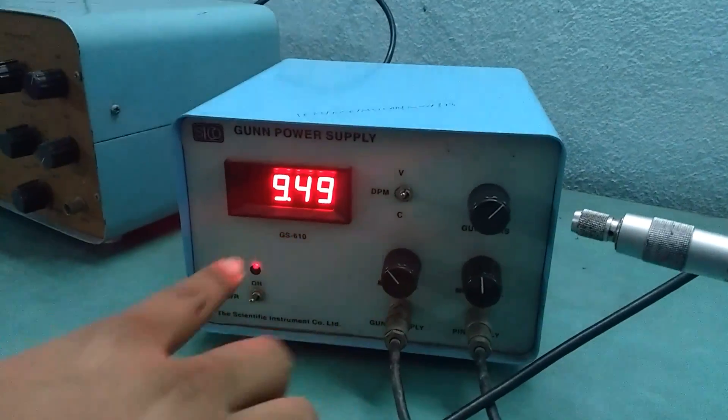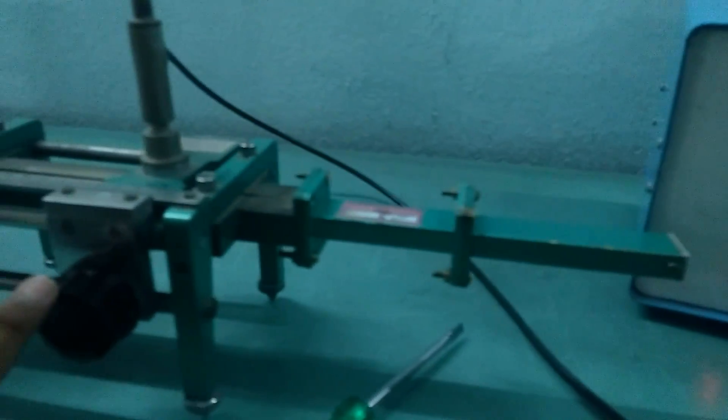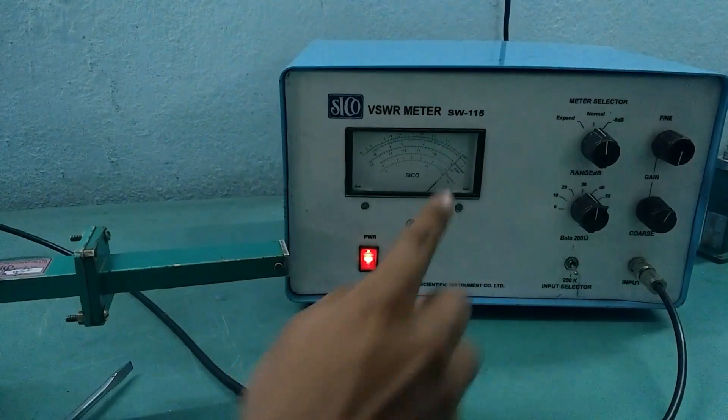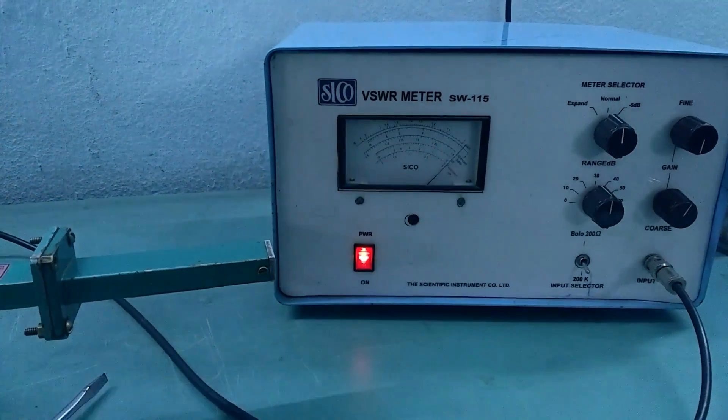We fix the Gunn bias voltage at 9.5 volts and move to the VSWR meter. As we can see, the position is at 0 now and we will shift it to get a maximum. A maximum deflection will be when the needle makes this deflection.